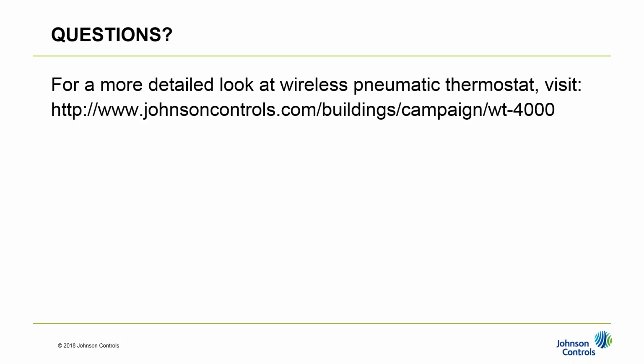Okay, great, thank you. Another key aspect—and we publish a best practices document to address some of these—is that we highly recommend having multiple paths back to the gateway. It's even helpful if the thermostat can reach the gateway by distance alone. If there's any interference or anything disruptive, having a second path for that thing to eventually get to the gateway makes it a much more robust system.